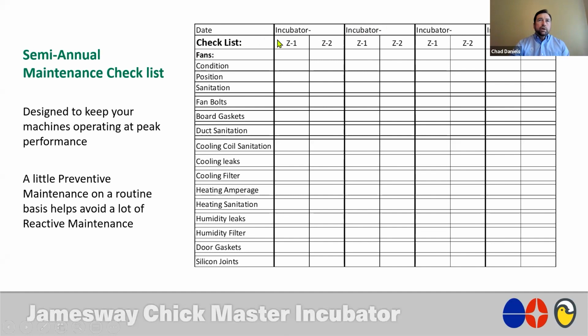So to begin with, we do break the incubator down on a per zone basis. So you do have a zone 1, zone 2, and we begin simply by focusing on the heart of the machine, the fans. When we look at this checklist, what I'm really trying to accomplish when I look at fans is I want to look at the condition, the position, and the sanitation of each one of these fans, all 6 of them, or if you've got a machine that's smaller and just has 4. But either way, the goal is to check these items. And I simply want to look at the 3 in zone 1 and put a check here that I've checked condition, position, sanitation, and do the same thing for zone 2.